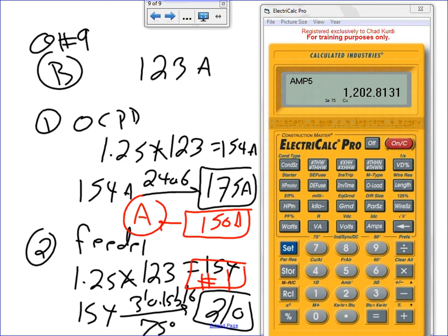For A, we calculated, we took 103 amps times 1.25, equals 129. Your next standard up is what? You have to go to 240.6. 150. Yeah. Then conductor-wise, you need to size based on 129. Go to the table. It should be one. I see. You size based on the load.